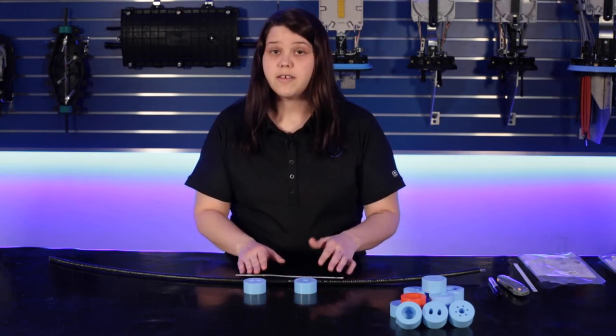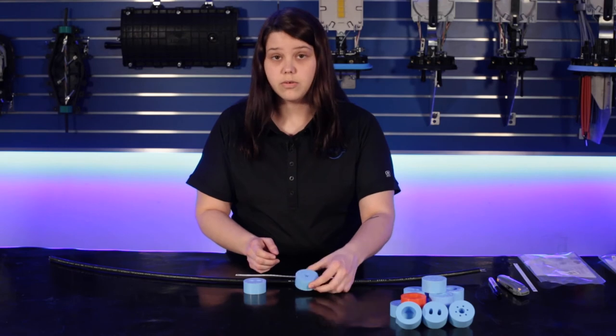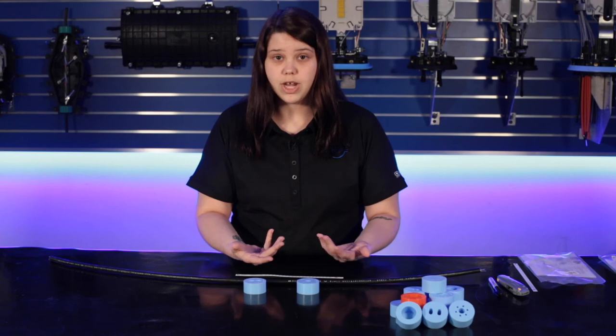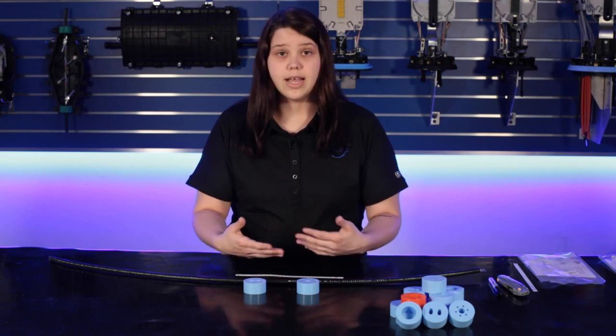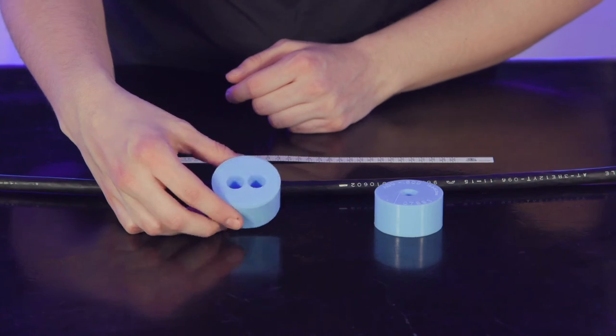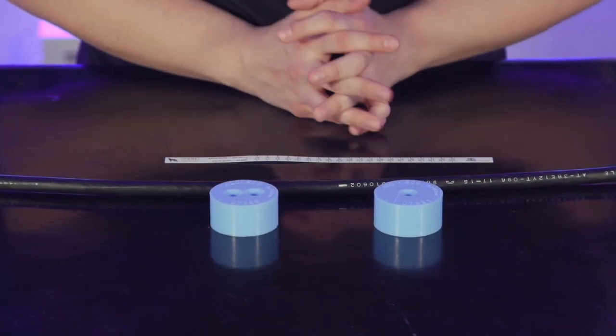Because this cable is going to act as my feed cable, I'm going to use the one-hole grommet. If you were using this cable for a branch application or you were going to add extra cables in, you can go ahead and use the two-hole grommet. But for me today, I'm going to pick the one-hole grommet.